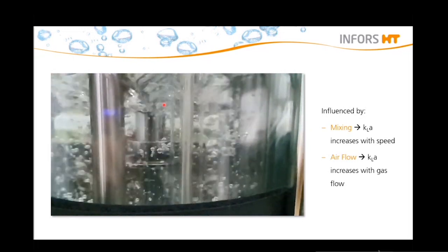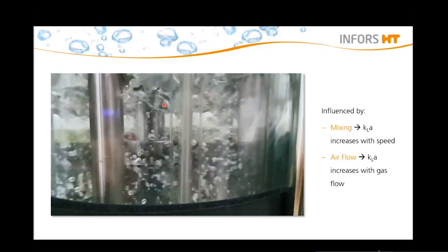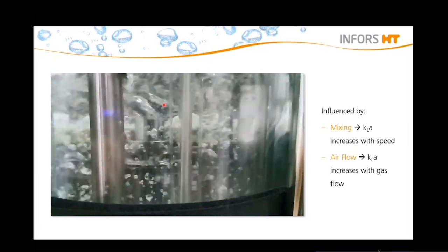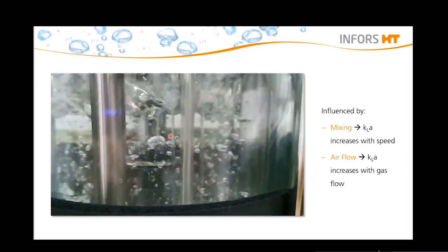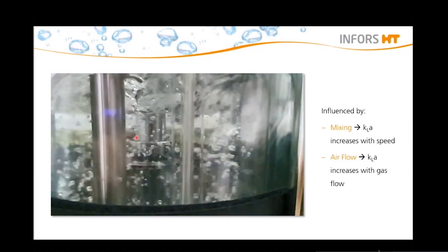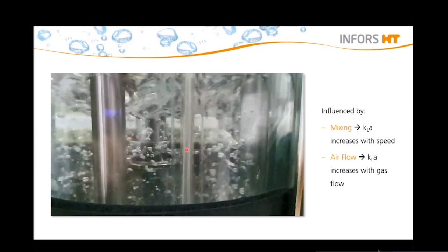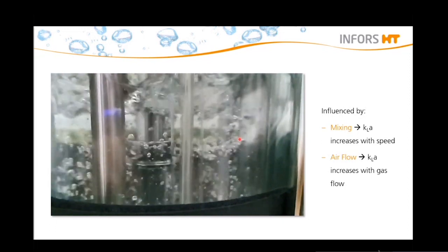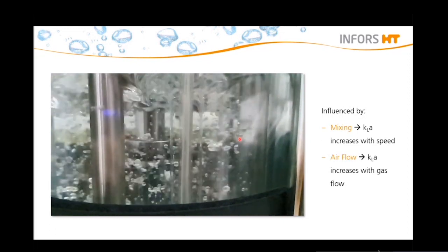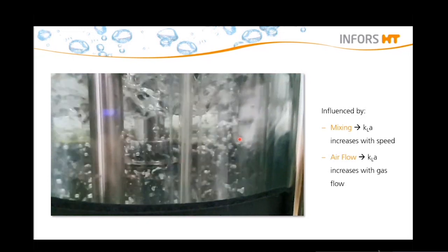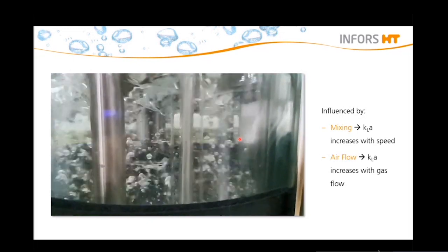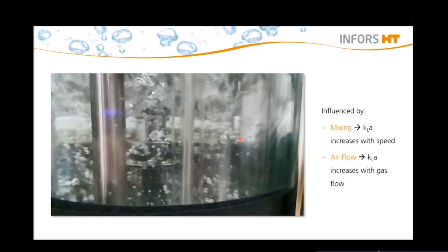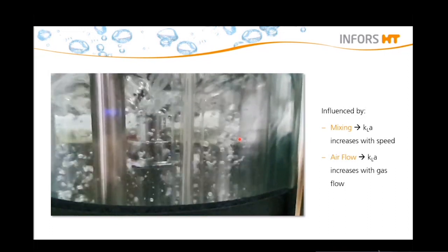But it looks like — wouldn't that be too harsh for the cells actually? I know the stirring in the video looks very harsh, but don't worry. It's a microbial system which has a Rushton turbine as impeller, as you can see here. For your cell culture process, you would use a so-called pitched blade impeller, which is much more gentle to the cells. Okay, that makes sense.